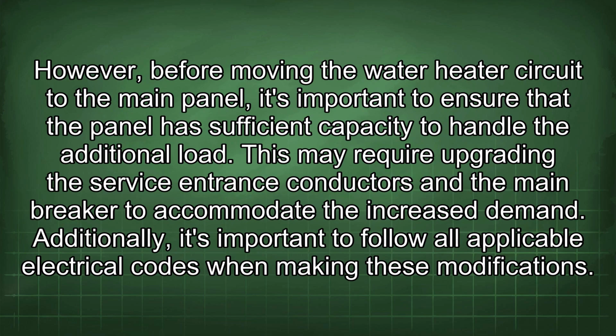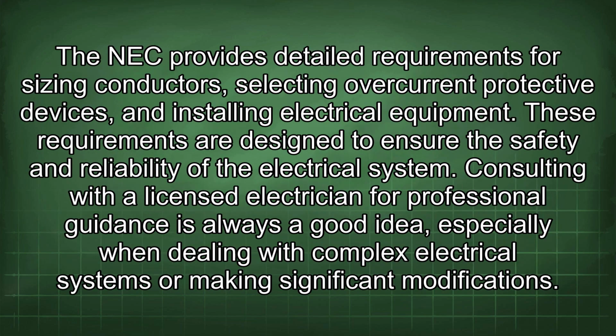However, before moving the water heater circuit to the main panel, it's important to ensure that the panel has sufficient capacity to handle the additional load. This may require upgrading the service entrance conductors and the main breaker to accommodate the increased demand. Additionally, it's important to follow all applicable electrical codes when making these modifications. The NEC provides detailed requirements for sizing conductors, selecting overcurrent protective devices, and installing electrical equipment. These requirements are designed to ensure the safety and reliability of the electrical system.